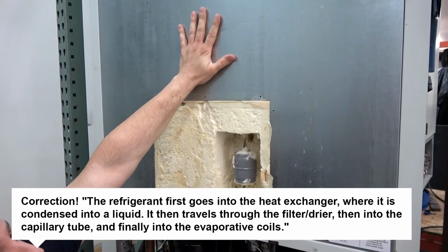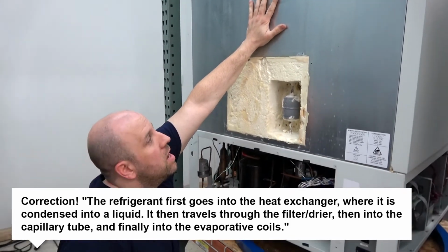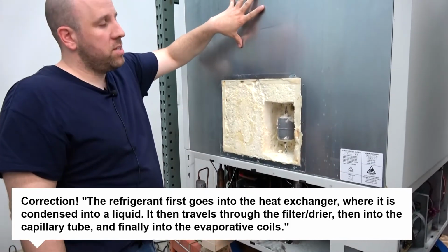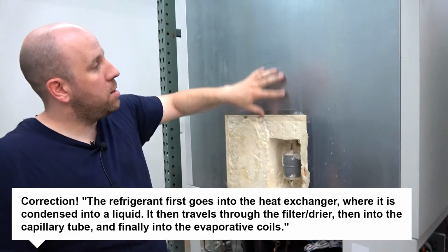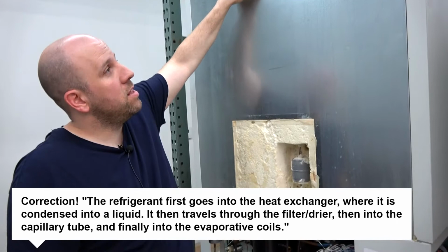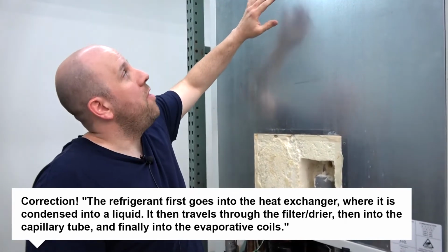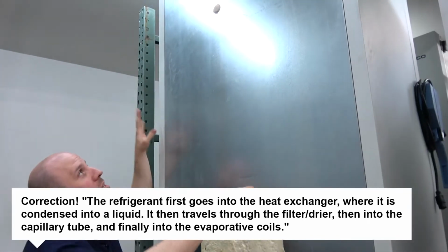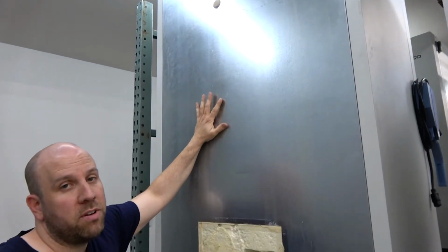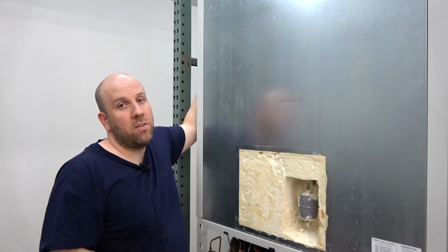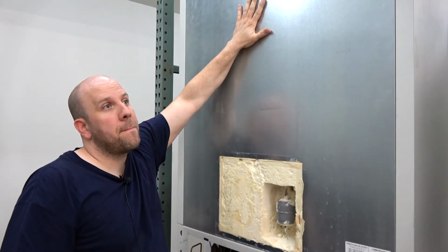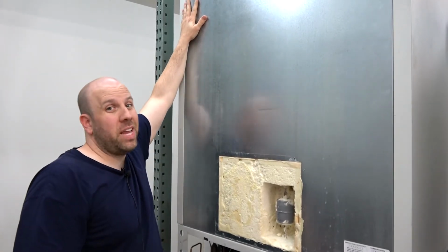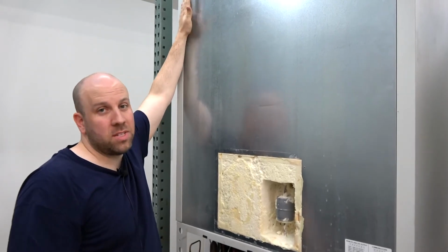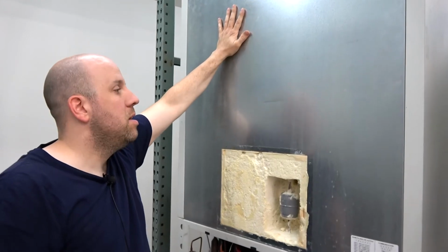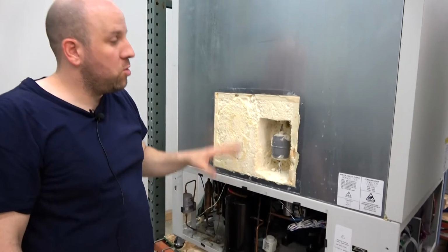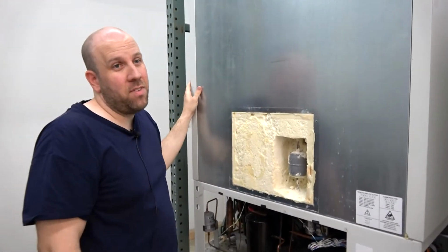So this up here will often reach negative 50 degrees Celsius. And then once it comes up, the second stage, it keeps coming up through after that. And at that point, it's a liquid at roughly negative 45 degrees Celsius. And then it goes into those tubes that we talked about that are spread all inside here on the top, sides, and whatnot. That's where the liquid refrigerant evaporates and sucks all the heat out of the chamber. And up to where it evaporates, it reaches negative 90-some degrees Celsius, depending on the situation and temperatures and things like that. But it's extremely cold. The first stage system can only get to about negative 50, and the second stage can get down to about negative 90 or so Celsius.